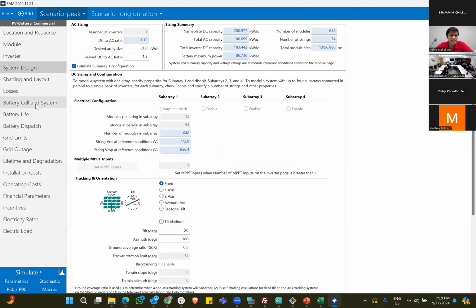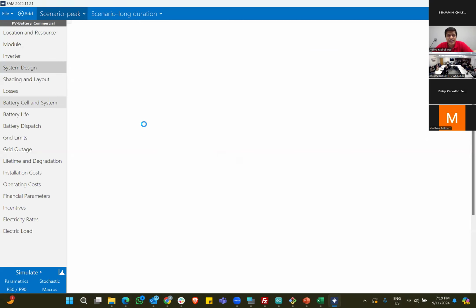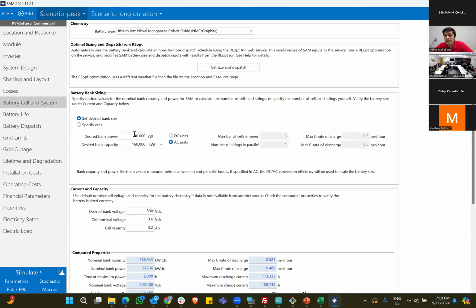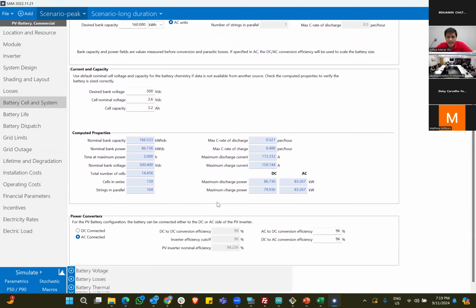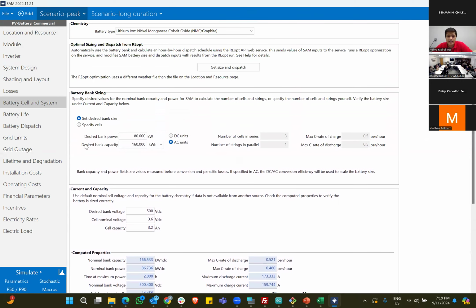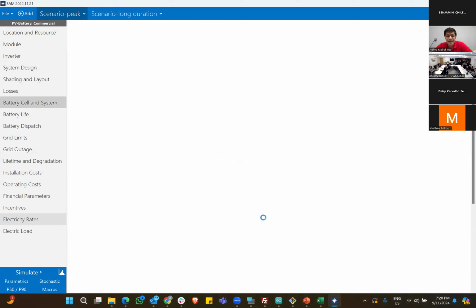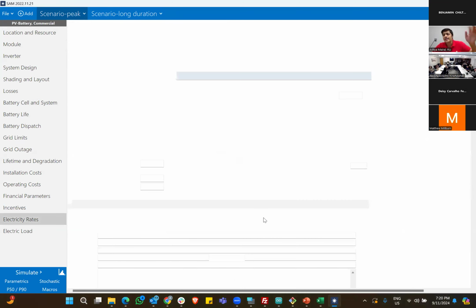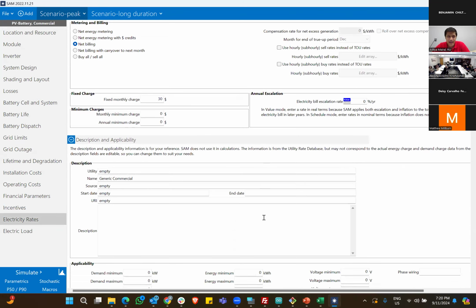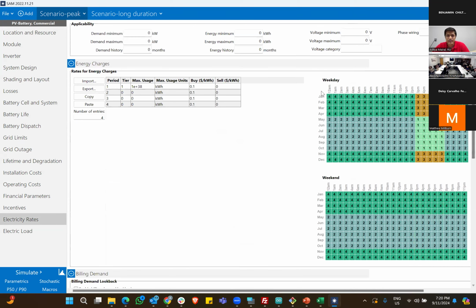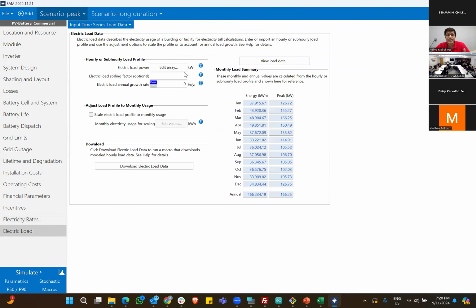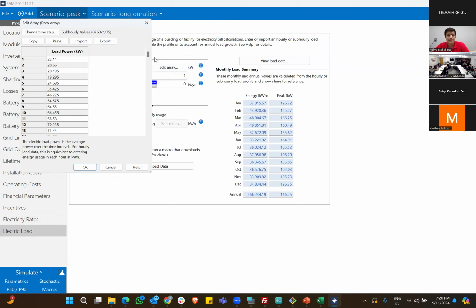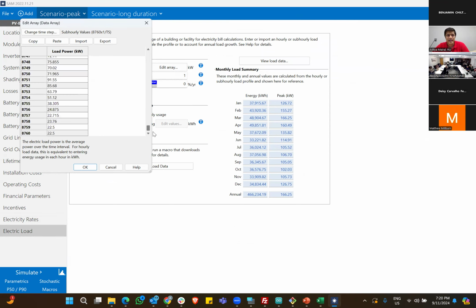Then I set up the battery cell: 80 kilowatts maximum power and 160 kilowatt hours to shave that peak, keeping everything else default. I added rates of $20 per kilowatt for demand and a flat 10 cents per kilowatt hour - this tool also lets you add different rates for different times of day. Then, very importantly, I added the electric load profile, the hourly array of loads.